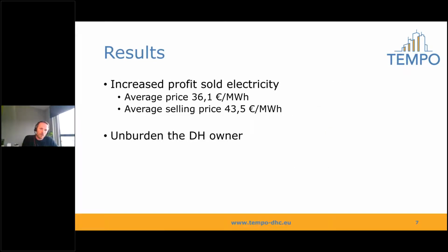An important advantage is that we unburden the district heating owner, because before, the district heating owner was putting in the CHP profile every morning and evening himself, doing calculations from experience in the past, seeing when it would be best to run the CHP. This now goes automatically. It can also decrease maintenance for the CHP, because we can keep into account all the constraints necessary on the CHP running time, so that we do not have to do an emergency stop, which is bad for the CHP.